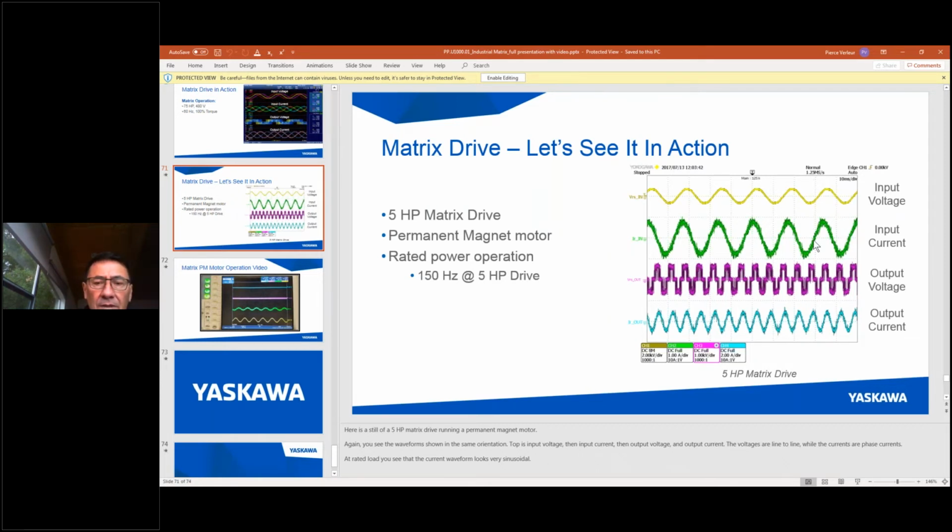They're sinusoidal, they have low harmonics. In the case of the input, it's compliant to IEEE 519 down to 30% of load. No filters. And a little parenthesis there, there's an EMI RFI filter which is on there to take emitted noise away to comply to the FCC standards, but it has nothing to do with our harmonic distortion compliance. And on the output, again, we have a good sine wave, which is what the submersible motor wants.